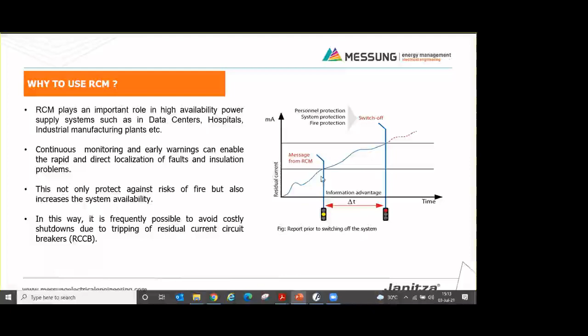Now, what are the problems caused by the residual current? It causes electric shocks, or it causes fire hazard. It can even cause problems to servers and computers, and it can cause fast corrosion of metal pipes. You would be surprised to know that residual currents of greater than 850 milliampere can cause corrosion to the metal pipes. It can also cause production shutdown.